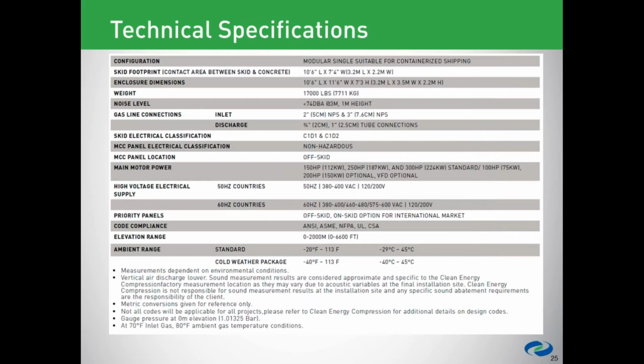Okay. Interesting question. How much will the noise increase without the enclosure? So that's something that we haven't tested, because in general the vast majority of our units go out with an enclosure. But these fans are rated around 85 to 90 decibels. So again, you lose that. That's at the fan itself. So the further you get away from that, the lower your noise levels. But we expect to see around 80, in that order, say 90 decibels at equivalent distance. Yeah, the only experience I have is actually having a conversation with all of the doors open and the unit running, and I was able to have a conversation at this volume level.